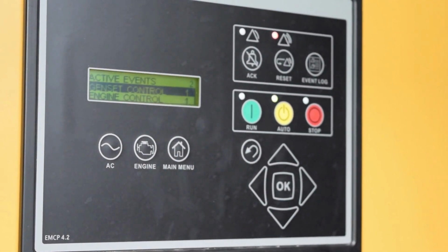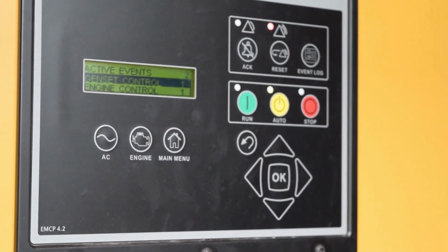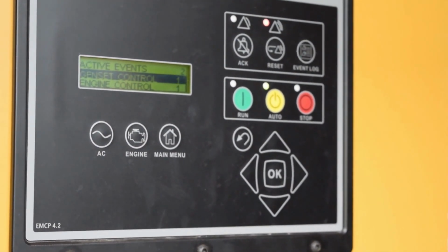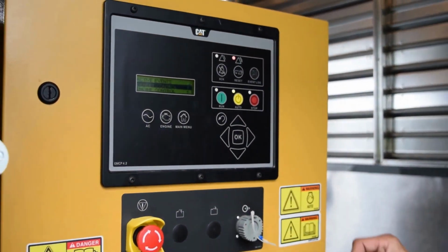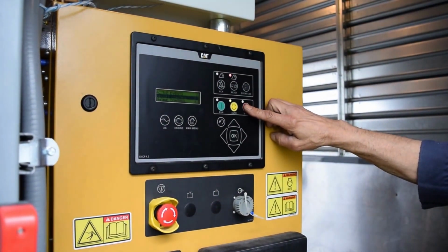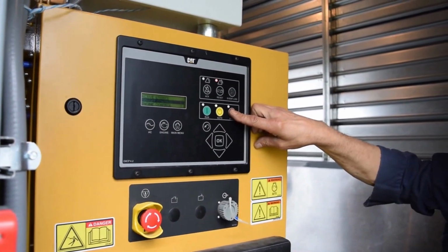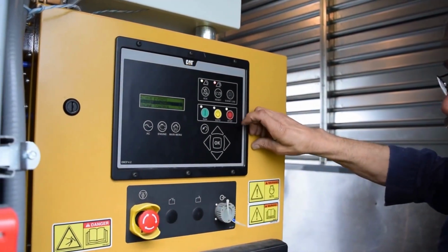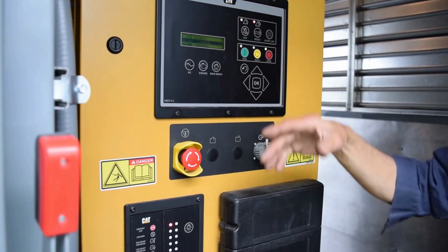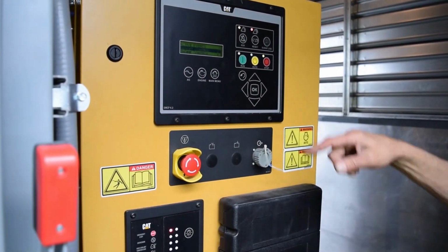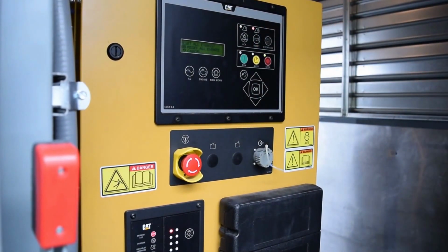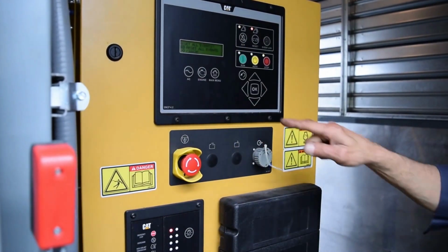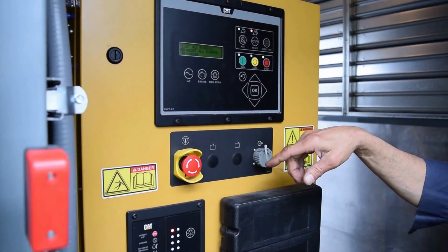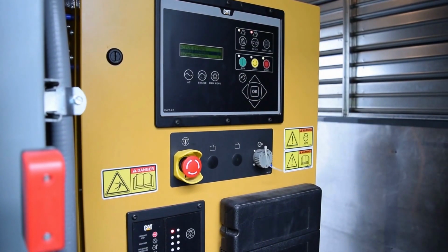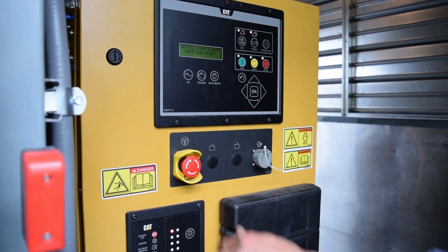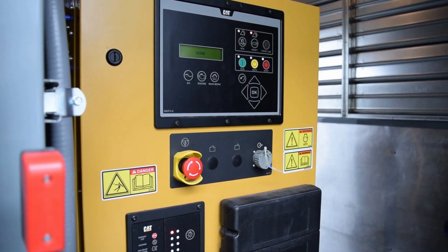So in order to reset any faults, it's 3 easy steps. You cannot reset a fault in automatic. And of course, nothing's going to happen if you go to run. So everything we do, it has to be in stop. So we're going to press the stop button, and that's going to give us an amber alarm for not in automatic. Then we just press the reset button, and it asks you, do you want to reset all the events? Hit escape if you don't want to. Hit OK if you'd like to. And nothing happened because I didn't correct the situation.